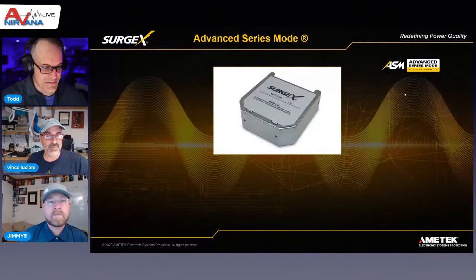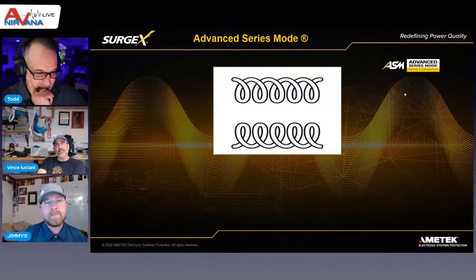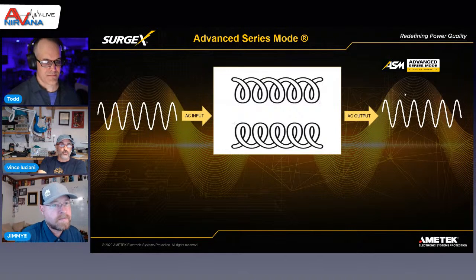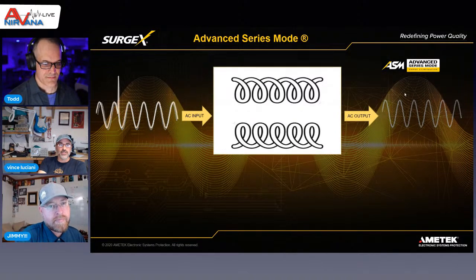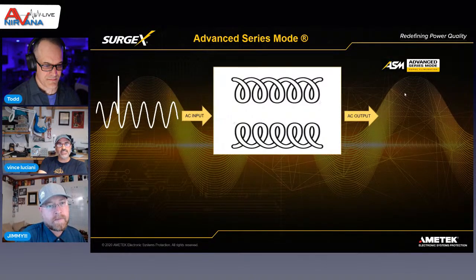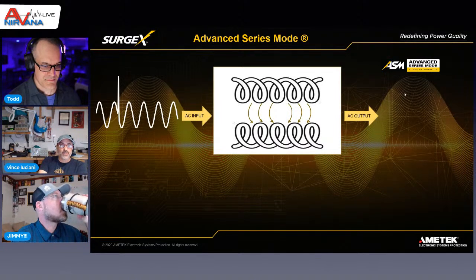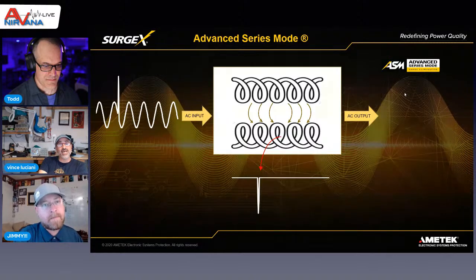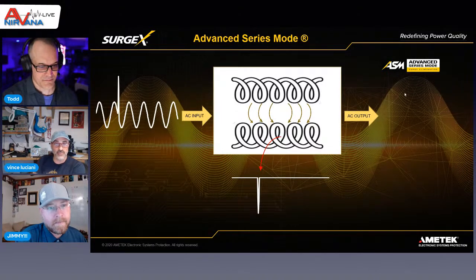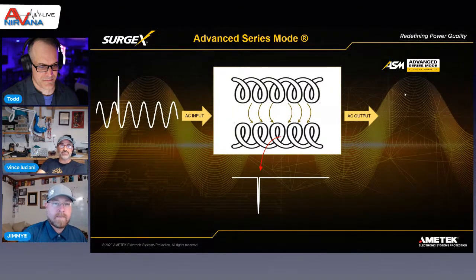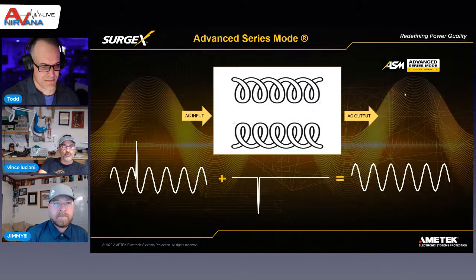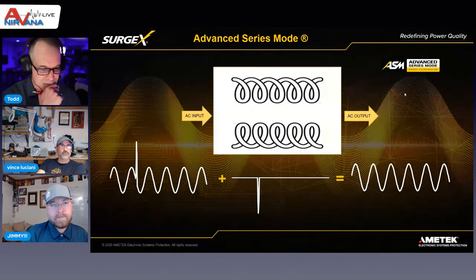Inside that big metal can is two air core inductors. When AC goes through the entire system and there's no surge, it passes right through, everything's good. If there's any surge energy on that AC waveform, through magnetic coupling, the surge waveform - since that's the high frequency part, and high frequencies can be capacitively coupled to other things - goes to that second inductor. That second inductor is wound backwards compared to the first, so we're creating an equal yet opposite surge waveform. When you add that to the original waveform, you effectively notch out the surge and let the AC pass through.